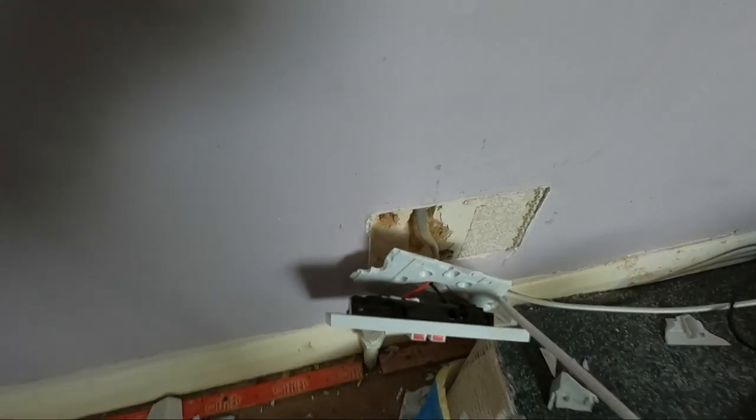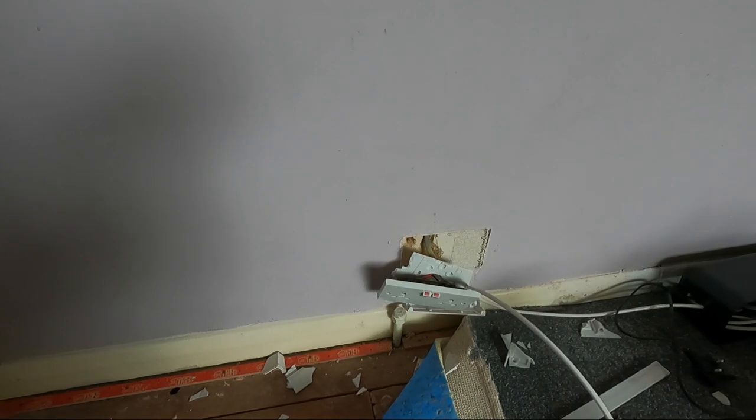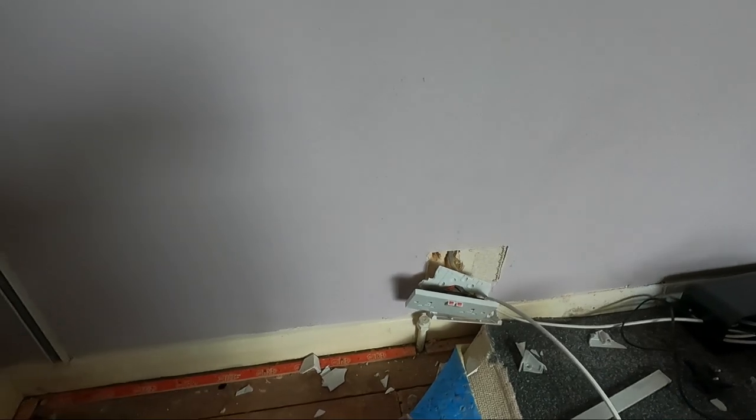Oh, we've got a cable coming down the wall. So, right. I remember this from upstairs. This is spurred from the upstairs sockets. So that's fine. But it means I was going to take a spur for a socket next to it. As we know, we can only have one spur from a ring, not another one. So yeah, this is coming from that JB that we found upstairs.